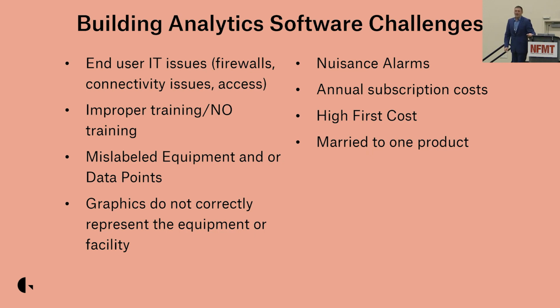Nuisance alarms. Does anybody here sit at the front end of a building automation system weekly? This is one of the biggest things people complain about. One of the funniest things I've seen is sitting with a controls technician who was getting so many nuisance alarms that it wasn't even a conscious effort anymore for the mouse to dart to the corner of the screen and silence the alarm while continuing to work. You'll see this if you spend enough time with controls technicians — they just stop paying attention to nuisance alarms. And sometimes alarms are important, but if you have 100 nuisance alarms and one important one, what's the point?